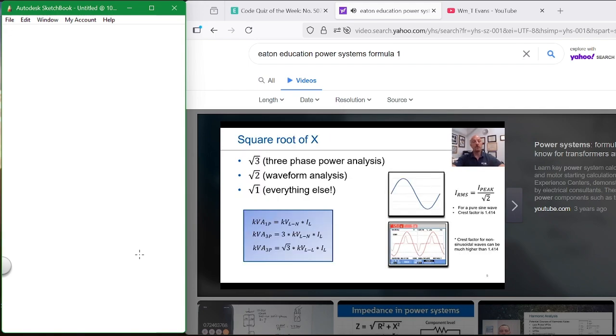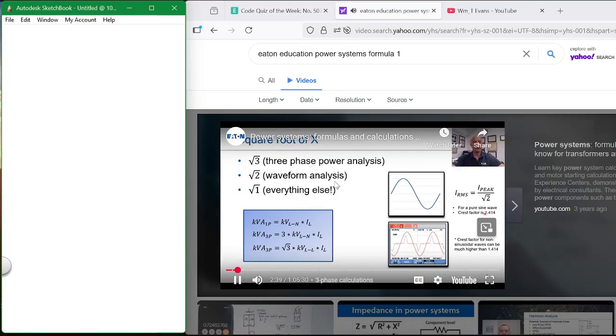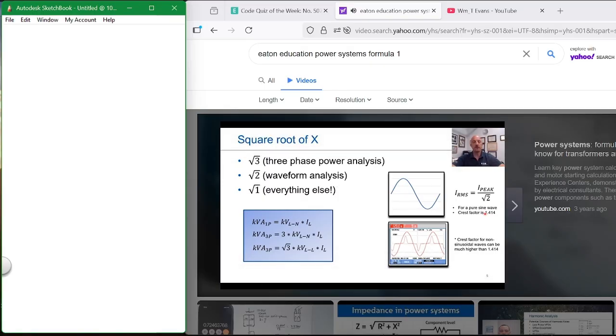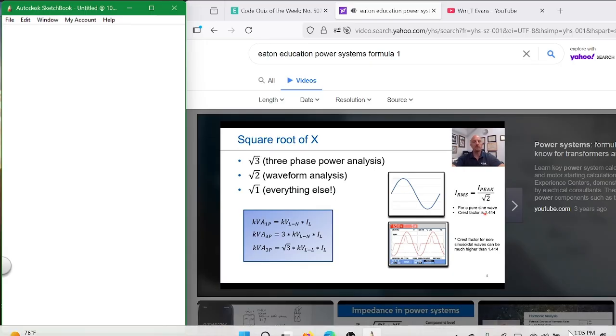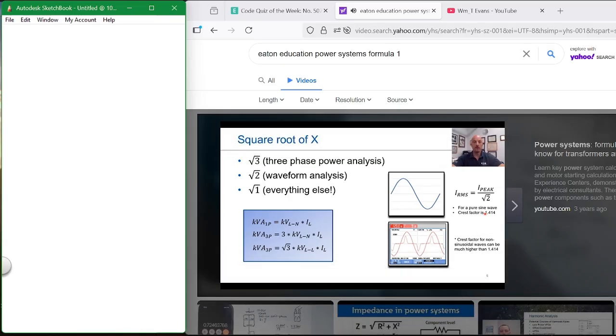Okay, so when do we use the square root of 3, the square root of 2, or the square root of 1? The square root of 3 is when we have three-phase calculations. Now, most people think that volts times amps equals watts, and we know that that's not true in AC power systems. Volts times amps equals volt-amps, or kV times amps equals kVA. So when we have single-phase power, we say kV line to neutral times I line equals kVA, single phase. If we multiply that by 3, we get the three-phase equivalent for a balanced system.